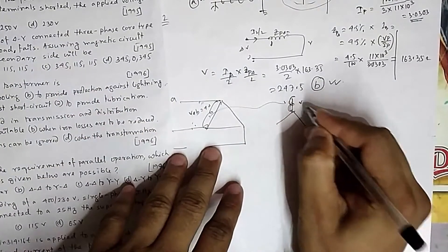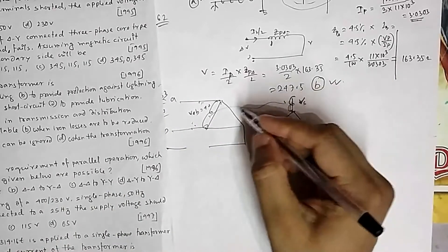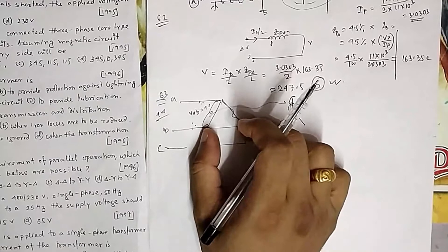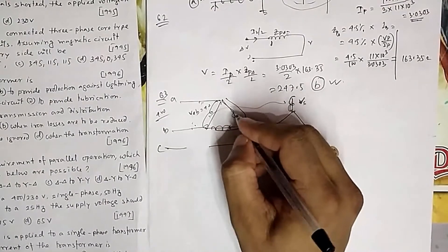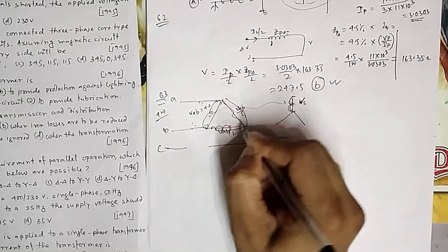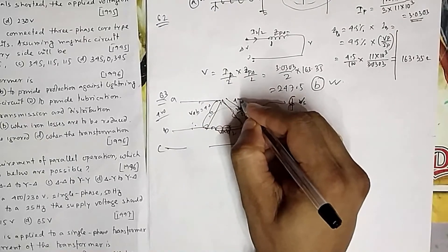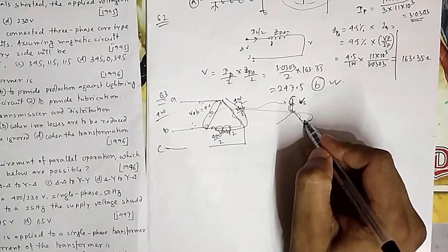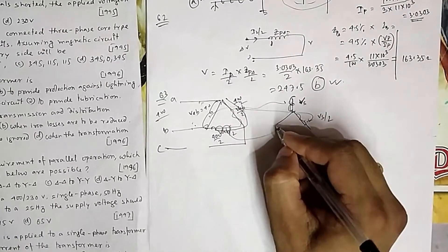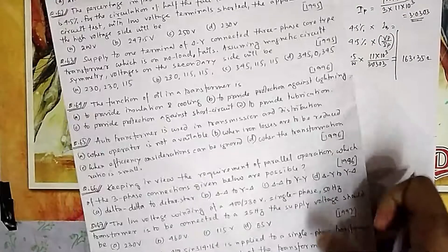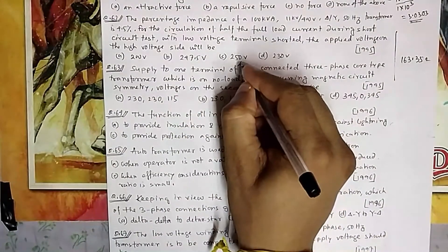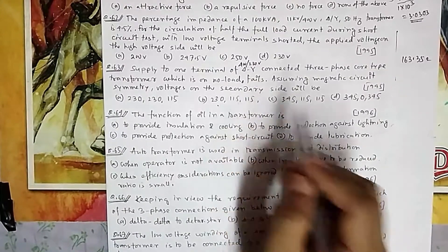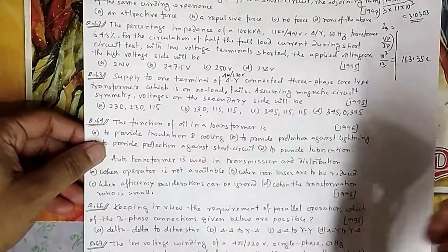The corresponding secondary winding gets its full rated voltage V_s. The other two delta windings — which were supposed to get V_AC and V_BC (each 400 V) — are now connected in series across V_AB, so each gets V_AB/2 = 200 V, which is half their rated voltage. Their corresponding secondary windings therefore induce V_s/2 each. So the three secondary voltages are V_s, V_s/2, and V_s/2. For a 400/230 V transformer this gives 230 V, 115 V, and 115 V — option B.